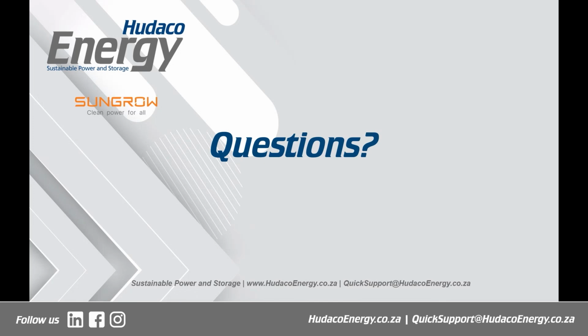JP? Can we unmute JP there? Yes, we can. Just give a second. So your export can be limited by kilowatts, or it can be switched off totally, based on the notified maximum demand of the house. Okay, so look, I think you're probably referring very much to what they do in Australia. Please bear in mind these products are rolled out all over Australia as well, and there I know they have limitations in terms of how much you can export there too. So yeah, you can limit. And Ian, you're saying on the 6 kilowatts, you can limit by kilowatts as well? Yeah, you can limit by kilowatts, percentage, or you can switch it off totally so that it doesn't export at all.